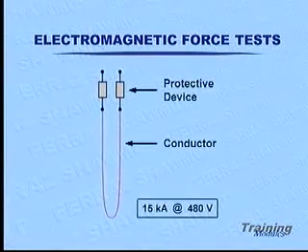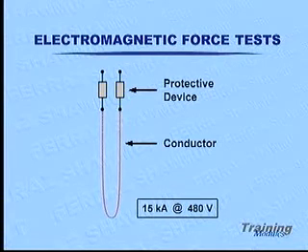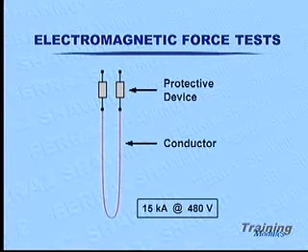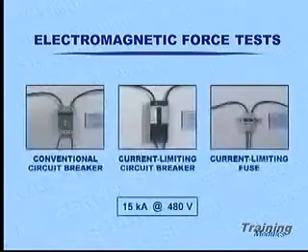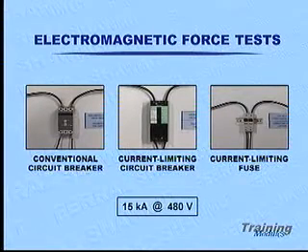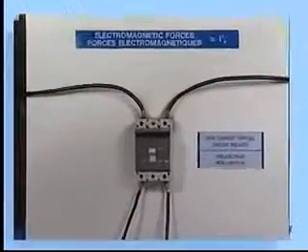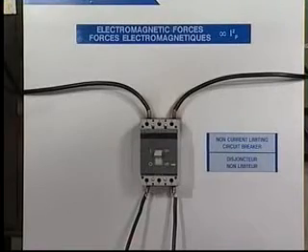For this first set of comparative tests, we have a length of conductor exposed to an available fault current of 15,000 amps, 480 volts. The three protective devices, all nominally rated at 25 amperes, are conventional circuit breaker, current-limiting breaker, and current-limiting fuses. The first test is the non-current limiting breaker.